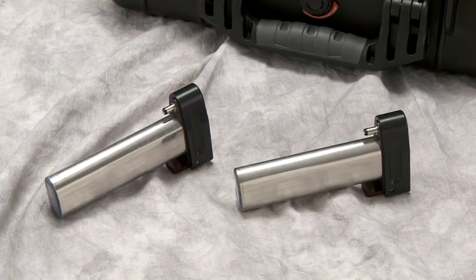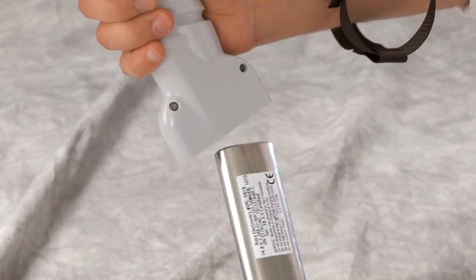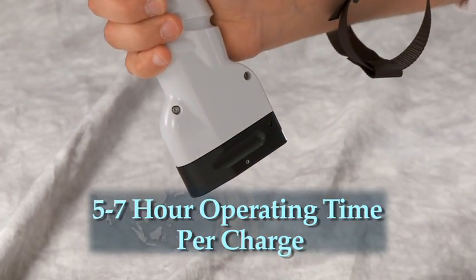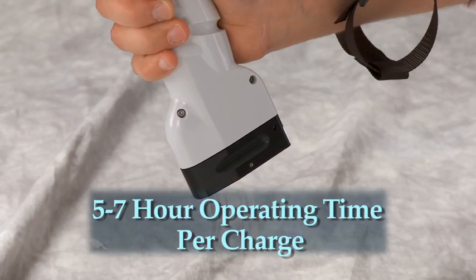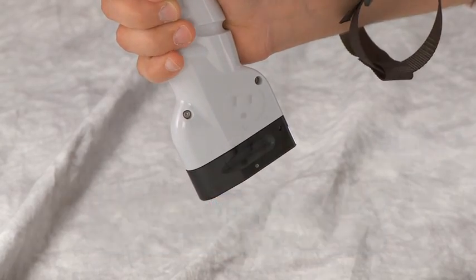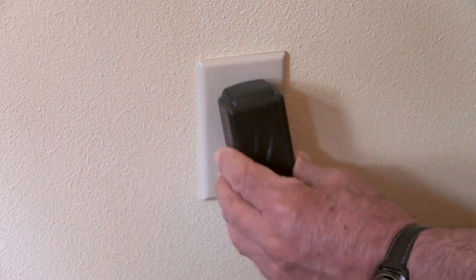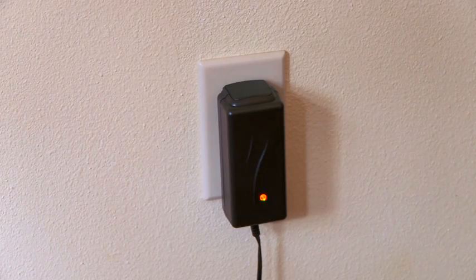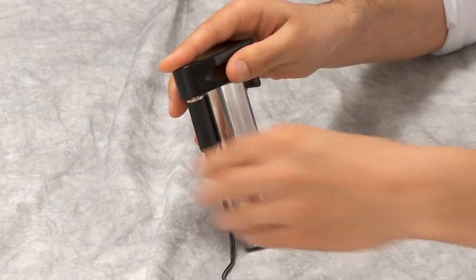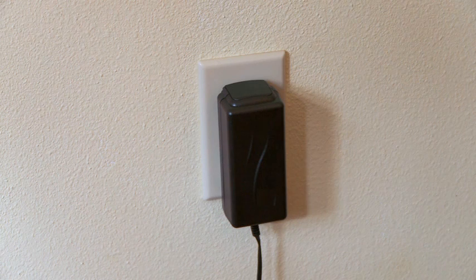Two lithium-ion batteries are supplied with the analyzer. Each battery, when combined with a fully charged PDA, can operate the analyzer for 5 to 7 hours. To charge the analyzer's battery, plug the battery charger into an AC line and then into the battery. While the battery is charging, the light on the charger will blink. When fully charged, the charger light will be on constantly.